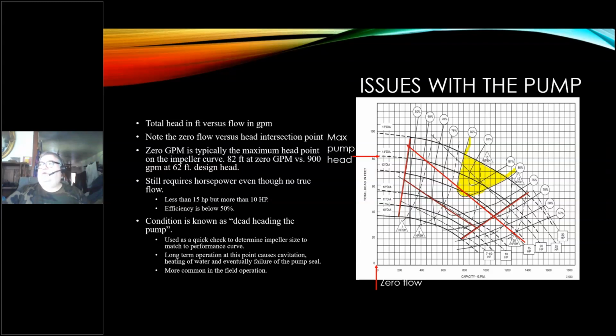And that means I'm using the right curve. If it says something else when I do that, I've got something wrong. Something's wrong. Somebody's done something to change it. Then I've got to check and see if I've got net positive suction head issues like that.